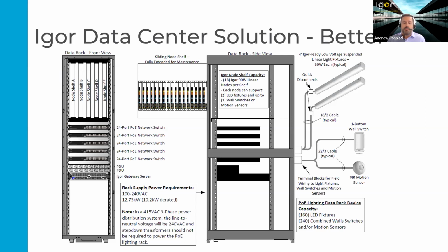So these can be flown in those same cable trays, right along with the data, the network cabling, because this is all DC-based power. So there's no AC noise, interference, etc., going through that. So it's not going to affect the data throughput of any of the other network cabling in those trays. And then also for any wall switches, motion sensors, etc., any other types of sensors, those would also have cables run through those cable trays back to the rack, landed on pre-labeled terminal blocks and such. So it's easy to trace, from one end to the other for troubleshooting purposes and such, where everything's going.